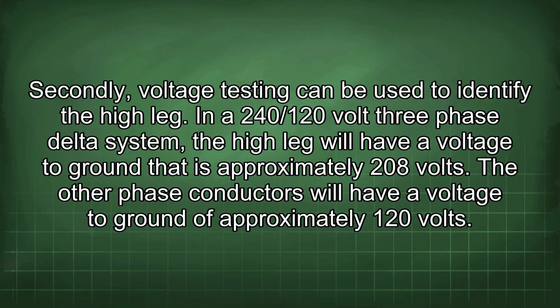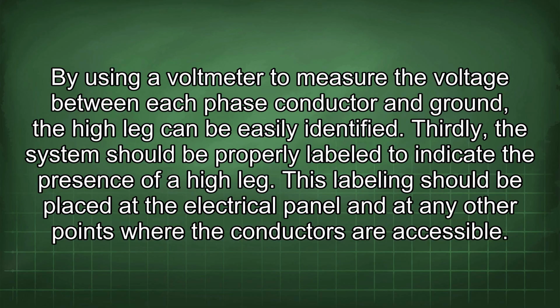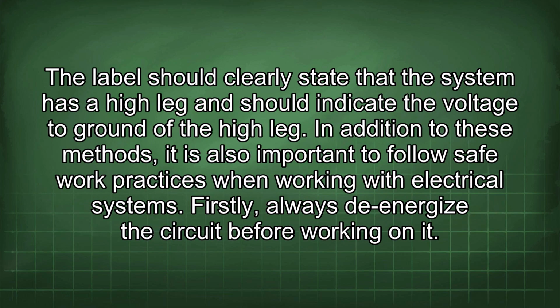Secondly, voltage testing can be used to identify the high leg. In a 240/120-volt three-phase delta system, the high leg will have a voltage to ground that is approximately 208 volts. The other phase conductors will have a voltage to ground of approximately 120 volts. By using a voltmeter to measure the voltage between each phase conductor and ground, the high leg can be easily identified. Thirdly, the system should be properly labeled to indicate the presence of a high leg. This labeling should be placed at the electrical panel and at any other points where the conductors are accessible. The label should clearly state that the system has a high leg and should indicate the voltage to ground of the high leg.